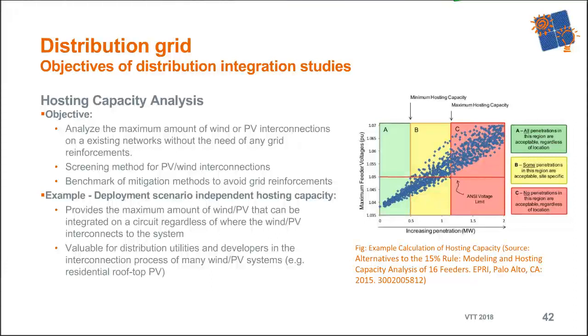You see that the voltage rise in the feeder increases with increased PV penetration, but also that if you're below 0.5 MW for this example, you don't have any voltage issues. So if you're a grid planner interconnecting PV systems across maybe a couple hundred feeders, you can see that below 500 kW there's no problem, so you can interconnect the system. This is a typical fast screen method at the distribution level, and I think the work by EPRI and others is already quite advanced on this.